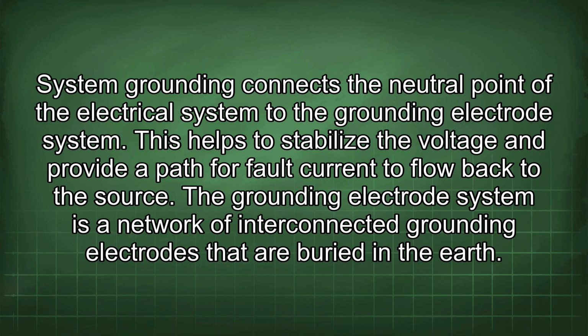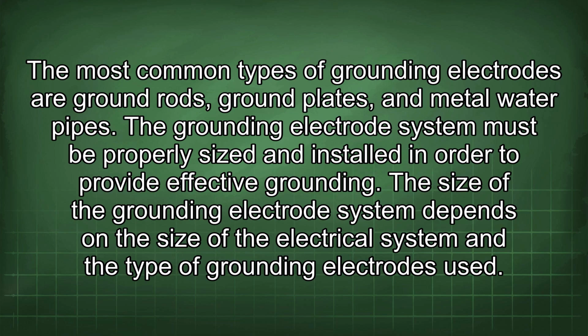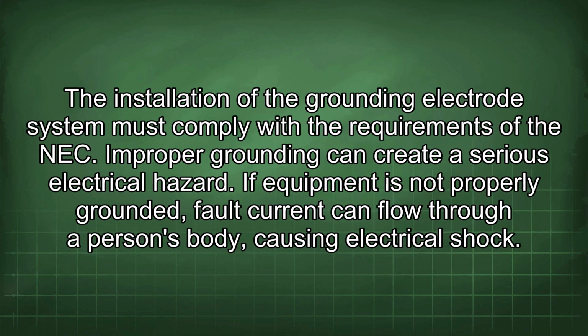The grounding electrode system is a network of interconnected grounding electrodes that are buried in the earth. The most common types of grounding electrodes are ground rods, ground plates, and metal water pipes. The grounding electrode system must be properly sized and installed in order to provide effective grounding. The size of the grounding electrode system depends on the size of the electrical system and the type of grounding electrodes used. The installation of the grounding electrode system must comply with the requirements of the NEC.